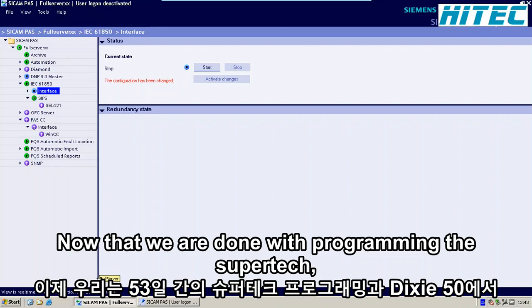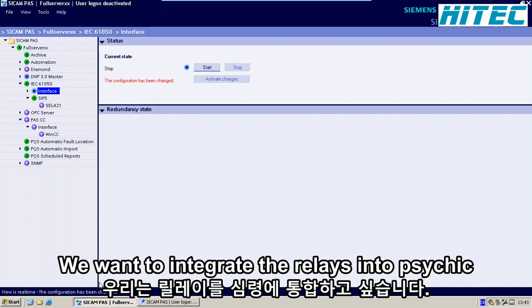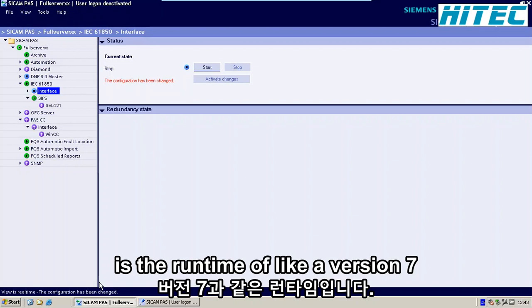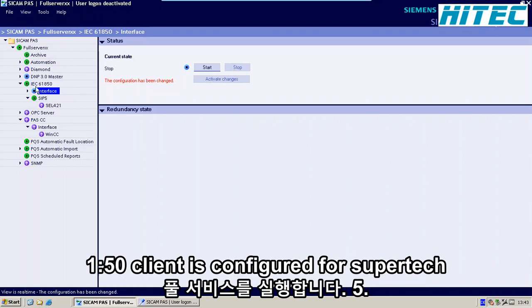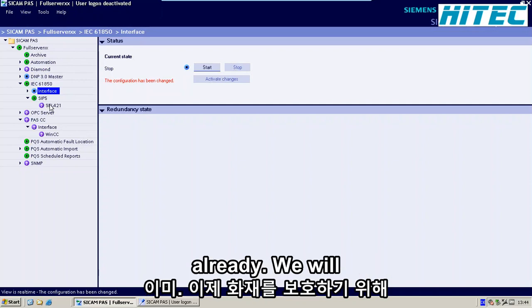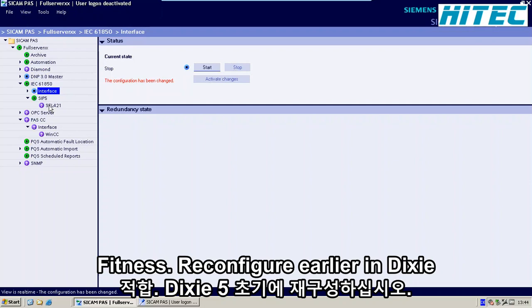Now that we are done with programming the SIPROTEC 5 relays and exporting the SCD file from DIGSI 5, we want to integrate the relays into SICAM PAS version 7. What you see on the screen is the runtime of SICAM PAS version 7. The full server is up and running and the IEC 61850 client is configured for SIPROTEC 5 interface with the SEL421 relay already. We want now to integrate the two SIPROTEC 5 relays we configured earlier in DIGSI 5.